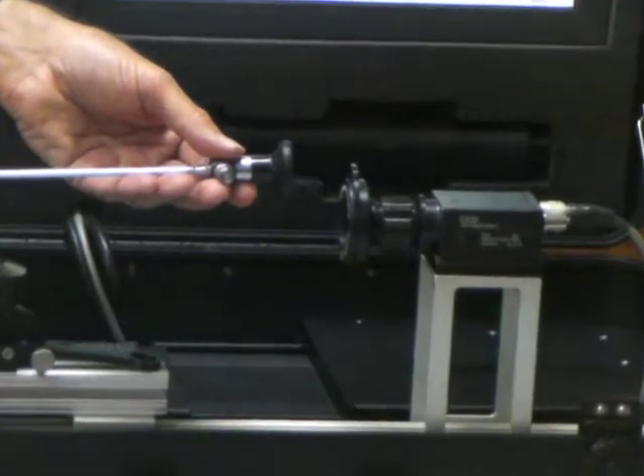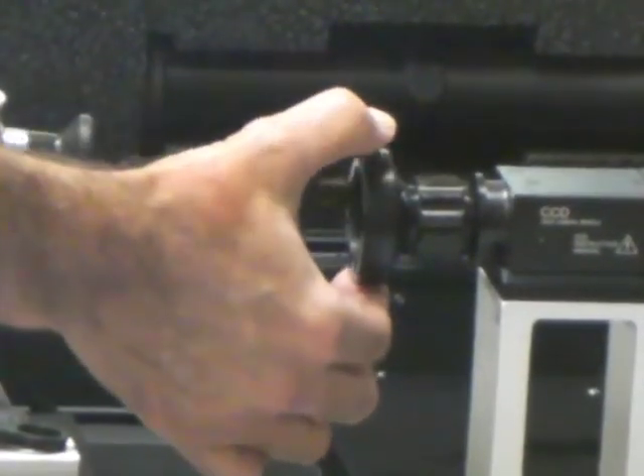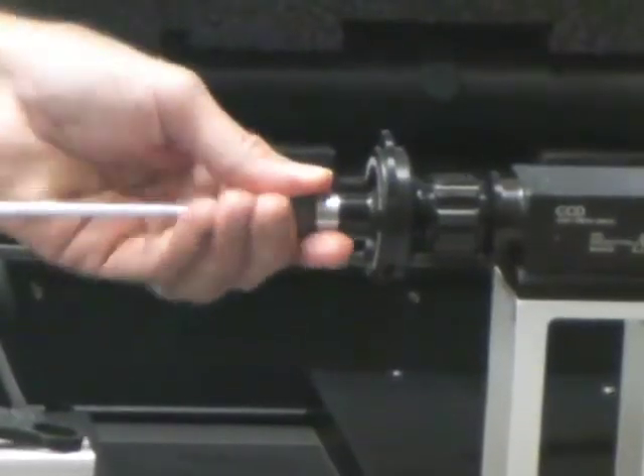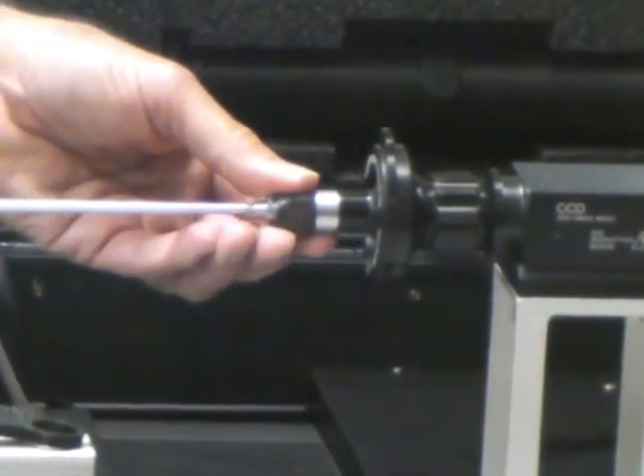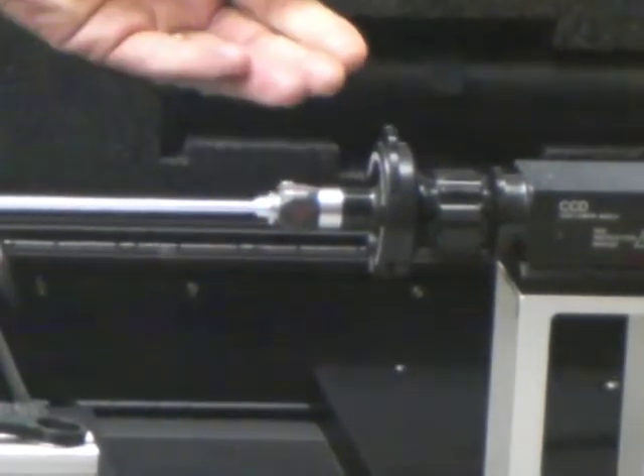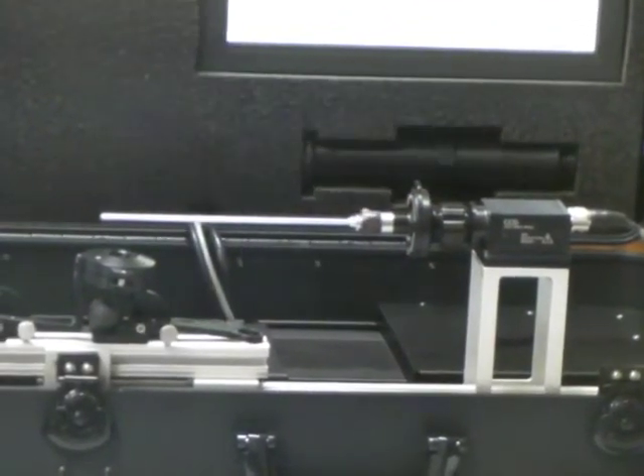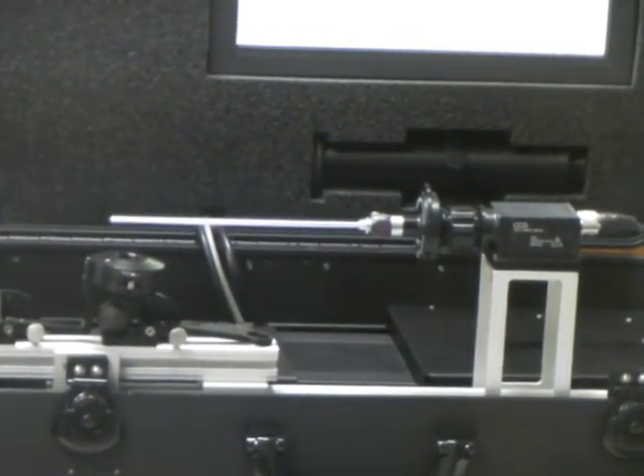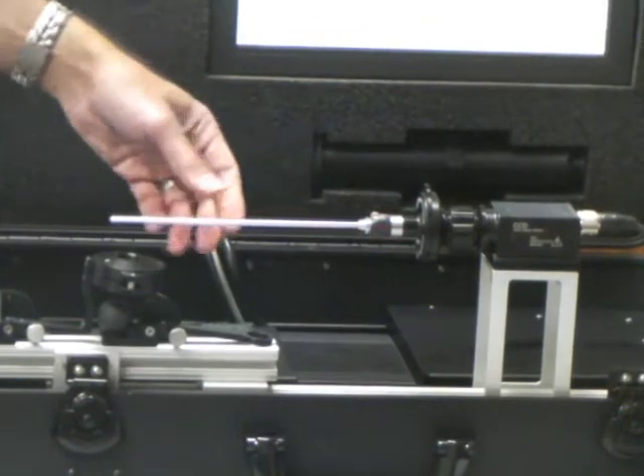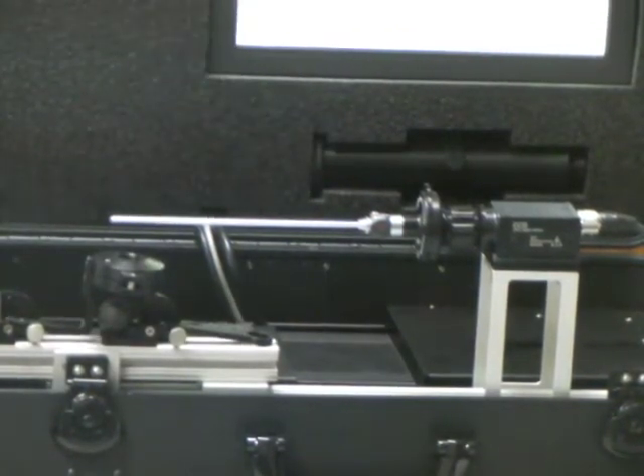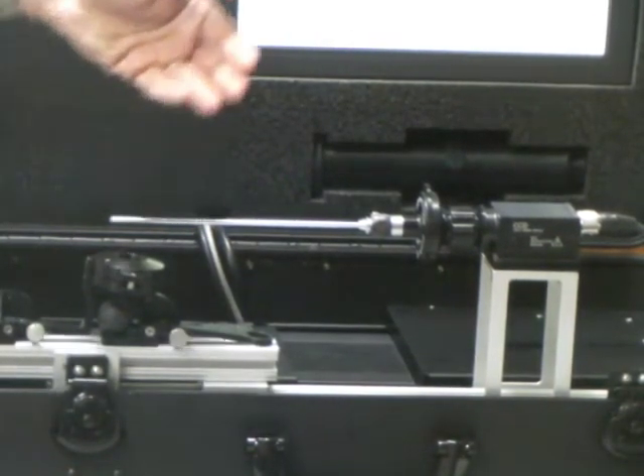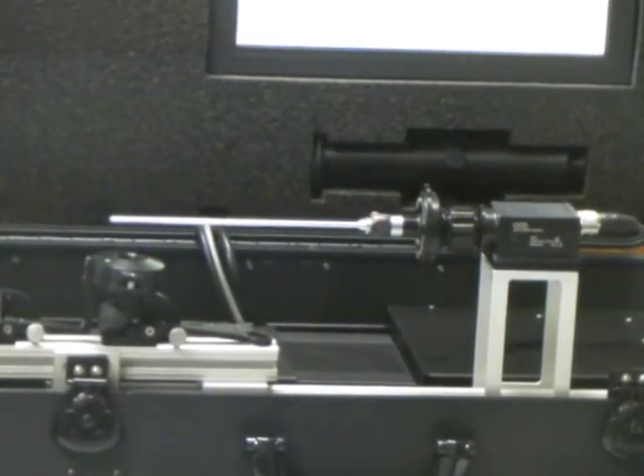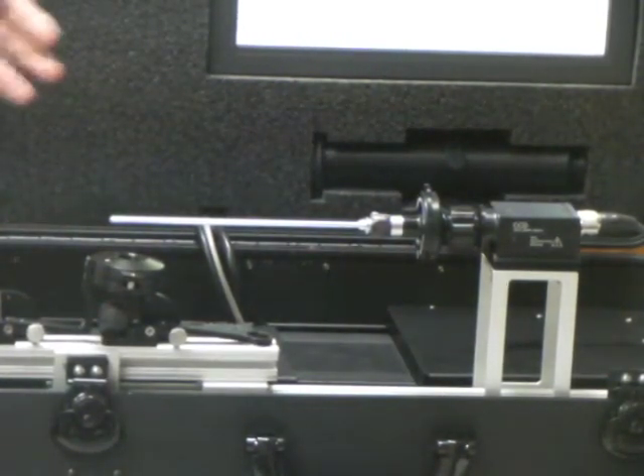To insert the endoscope into the Dragonfly, we just depress the plunger, insert the endoscope, and then release. And you can see that it's able to be rotated, but it's held rigidly. Anybody who's used an endoscope in surgery will recognize this is one of the popular means for attaching endoscopes to endoscopic cameras. And fortunately, the geometry of the eyepiece is somewhat standard. There's a DIN standard for the shape, and so if the endoscope manufacturer adheres to this standard, it'll work in the Dragonfly, and virtually all endoscopes do work in this eyepiece.